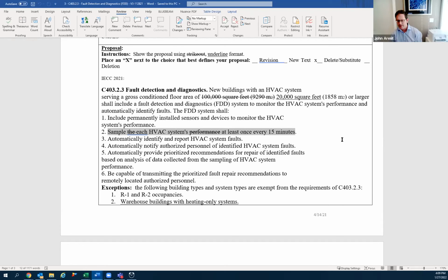Yeah, so I think that if it's not specified clearly enough, we can elaborate on the details of what would be tested. It's basically to get information on the system sensors, the outside air damper positions, the economizer status, and also to check that there are no system faults. So these things can be sampled or reported, and then reported to a central interface.